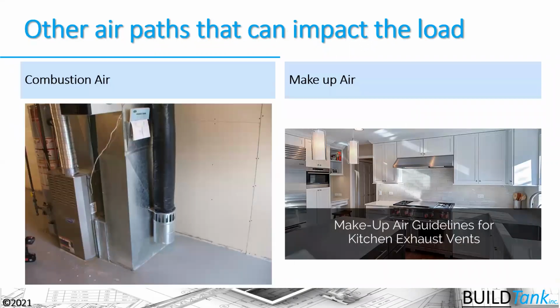The last thing I wanted to point out is there are 2 other air streams that aren't accounted for very well. One is combustion air, which is accounted for in our IECC code, and I'll show you that in a second. But the other is makeup air that's coming into the house for kitchen hoods, for example. The code says that you have to provide makeup air. So if you're providing makeup air, you might add an additional appliance to your load in that house for that makeup air, so that you're at least taking that into account in some way there.